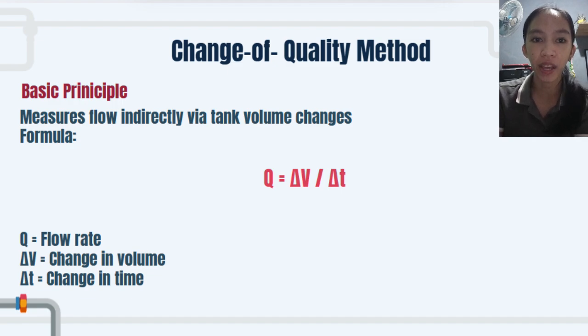This is an indirect way of measuring flow. The principle is simple. We use a level sensor to see how much fluid is in a tank at the start of a period and again at the end. The change in volume divided by the time it took for the change gives us the average flow rate. It's a straightforward application of this formula.